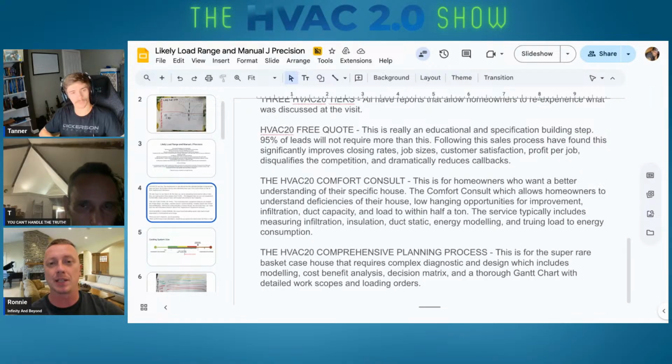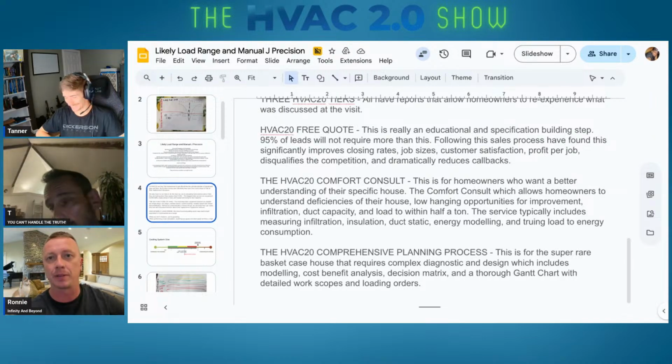Austin even went and tested his brother's house, one of the owners, that's always had a 4-ton system in his house since 2008 when the house was built. And he's had 3 compressor failures since 2008. And I'm talking about geothermal systems with compressor failures. Ouch. Good Lord. So Austin went and tested his house, and this was the first season that it has run on a 3-ton.